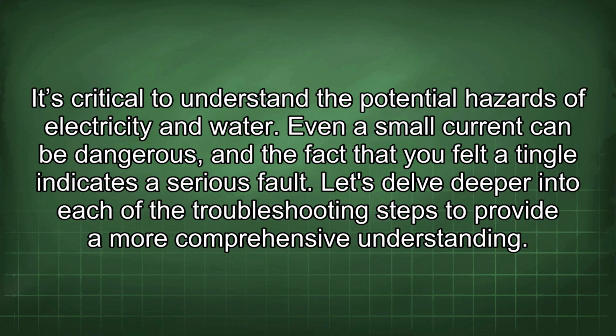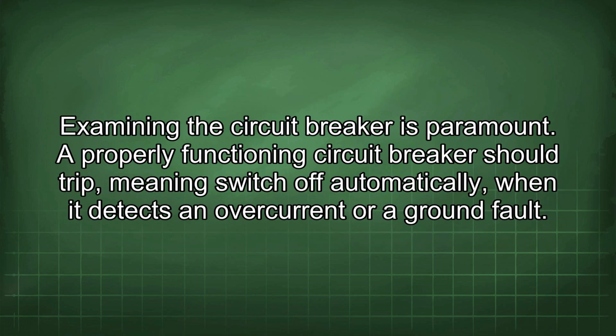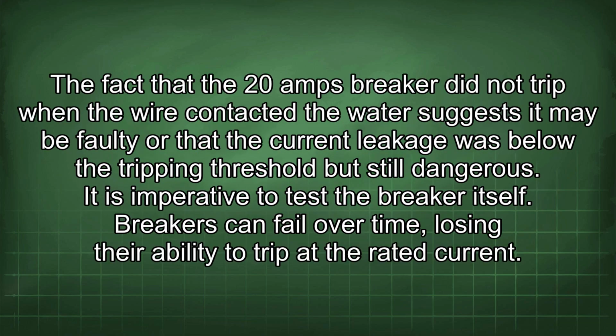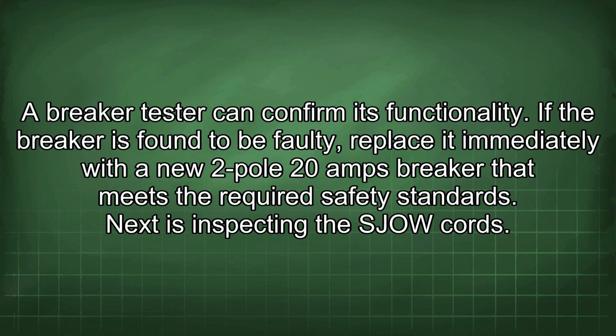Even a small current can be dangerous, and the fact that you felt a tingle indicates a serious fault. Let's delve deeper into each of the troubleshooting steps to provide a more comprehensive understanding. Examining the circuit breaker is paramount. A properly functioning circuit breaker should trip, meaning switch off automatically, when it detects an overcurrent or a ground fault. The fact that the 20 amp breaker did not trip when the wire contacted the water suggests it may be faulty, or that the current leakage was below the tripping threshold but still dangerous. It is imperative to test the breaker itself. Breakers can fail over time, losing their ability to trip at the rated current. A breaker tester can confirm its functionality.